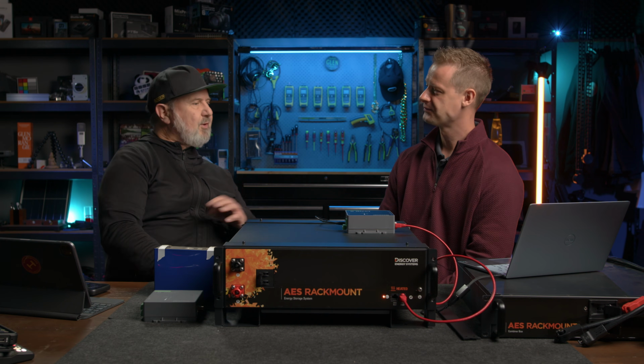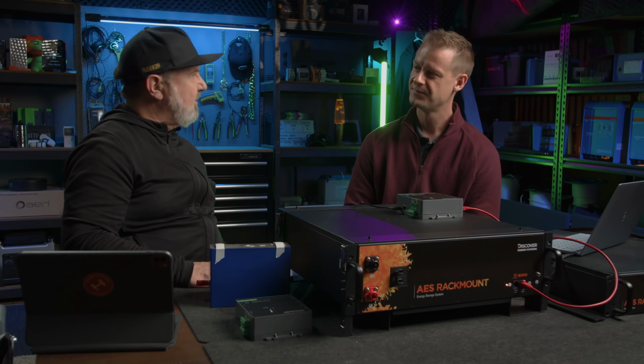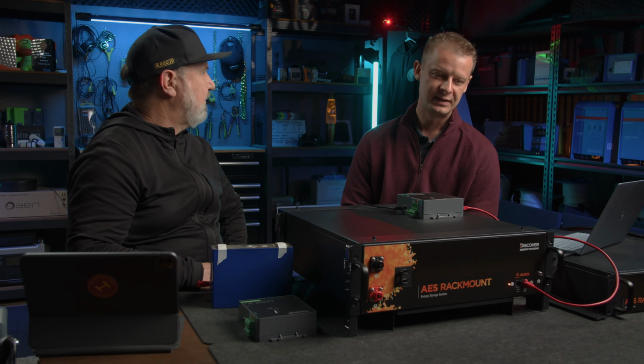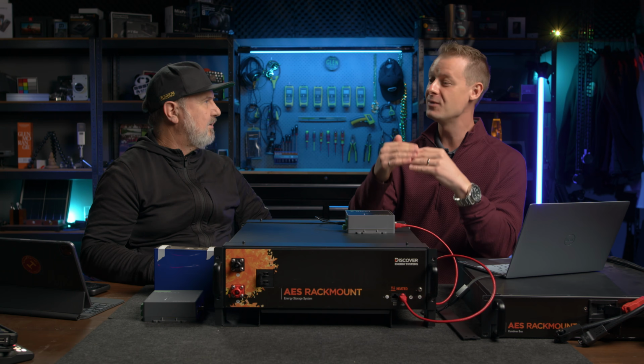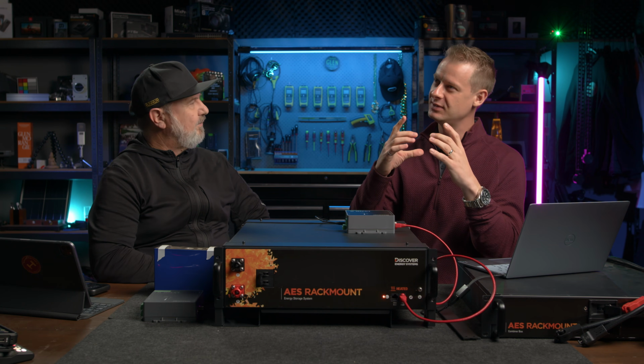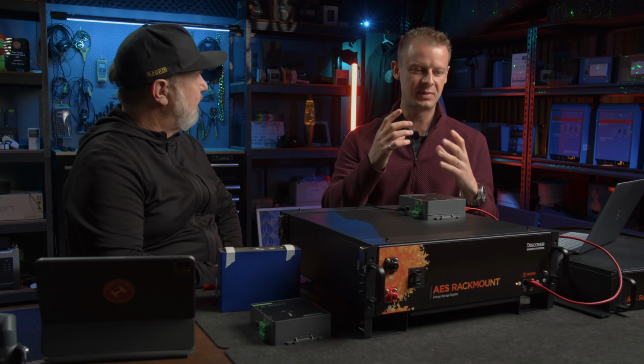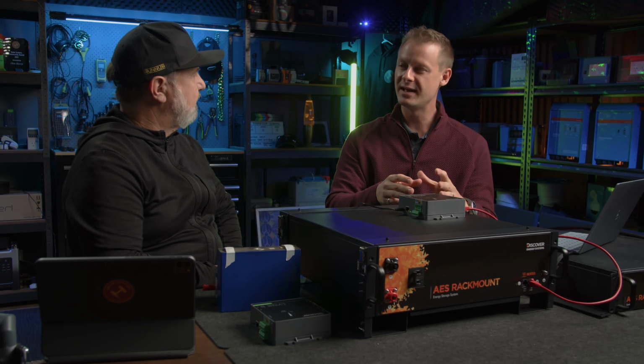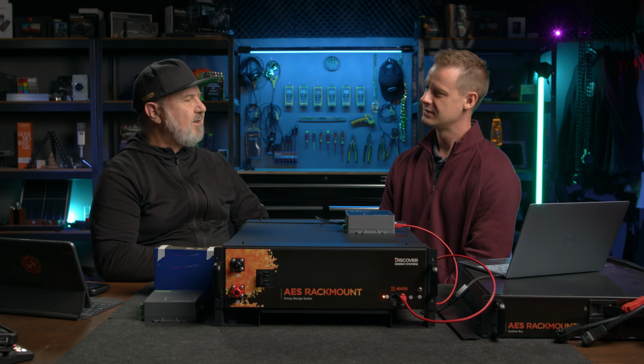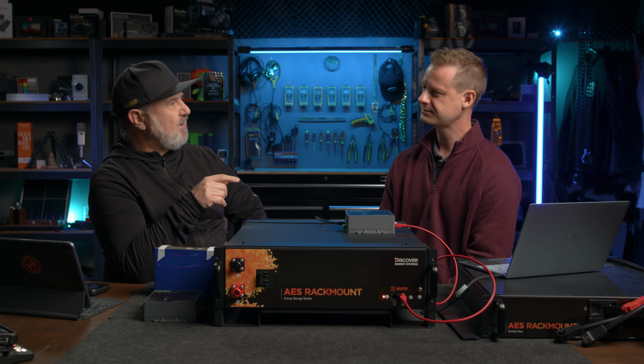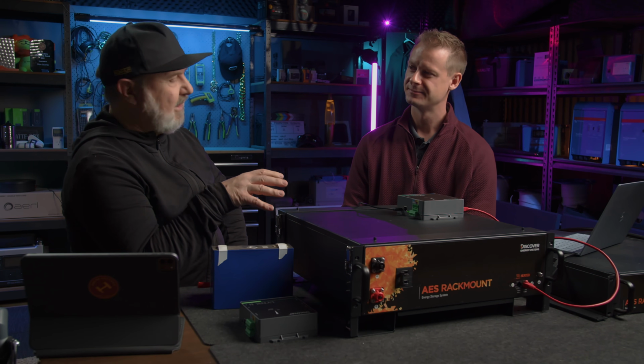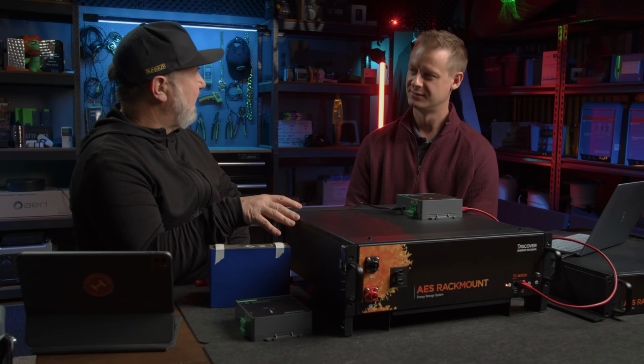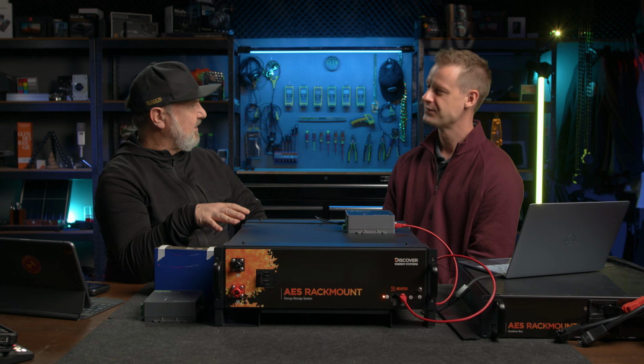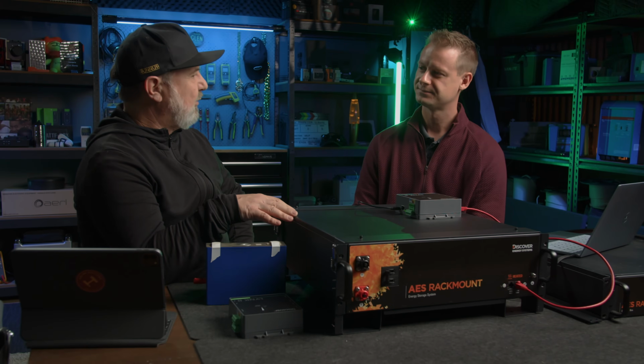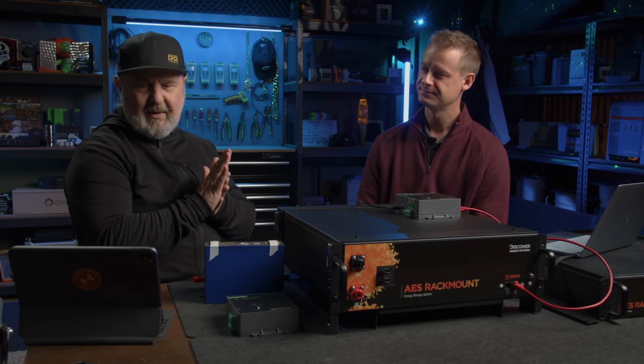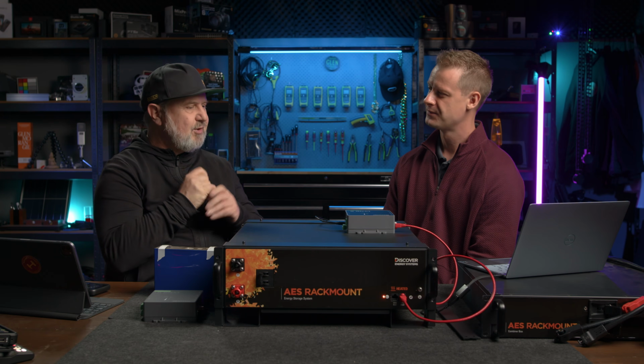At what point do you transition to that balancing phase? In truth, I guess the algorithm's always thinking of it, but you really see its strength when the batteries are taking in about an amp each. Because I've seen some self-managed batteries where there's a request that they go through an equalization phase at least once a week to ensure balancing happens properly. But with dynamic active balancing or active charging, are you constantly trying to balance?